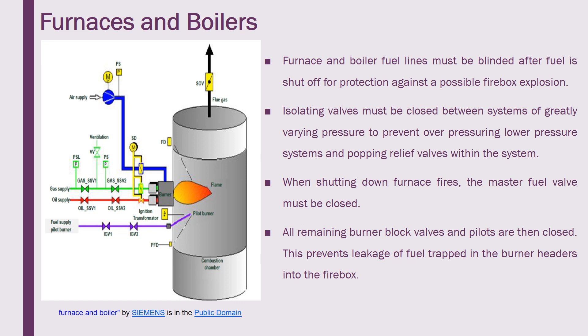The fire bricks that form the furnace walls are designed for long-term use and cannot easily be replaced. Sometimes a particular area of the furnace wall may be damaged but the entire furnace wall is not changed. So while doing unit clear with the furnace and boiler, remember: the master fuel valve should be closed, the pilot burner should be closed, and we must reduce the feed line and flow. The coolant inside the coil must be reduced in pressure in a gradual manner, not with sudden decrement.